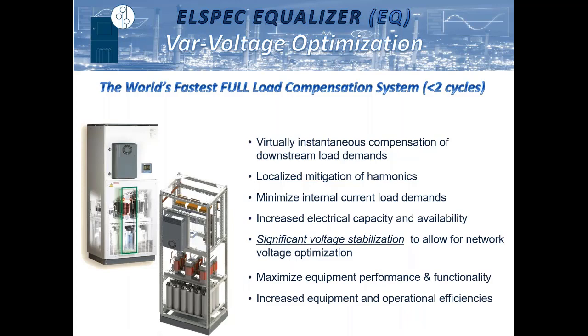can have a really important impact on the voltage levels. And that's really the main benefit and the purpose of the equalizer system: by accounting for all of the downstream load demands, we can create a much more stable environment, which can allow for all of the equipment to actually function and perform more efficiently. Because we're stabilizing that voltage level to a very, very tight bandwidth, we are basically putting the equipment back into more of a laboratory type condition, versus having a very volatile network where there's constant fluctuation of loads that are having an impact on the voltage throughout the network.